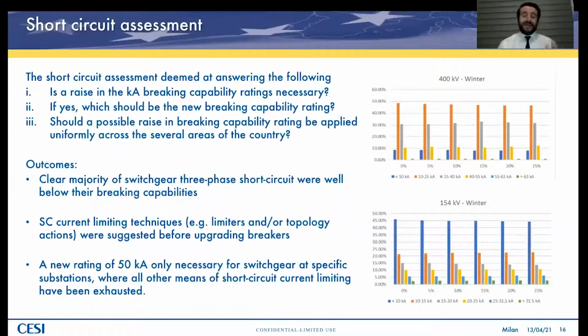Short circuit was at the time one of the major concerns for TEIAS, because the short circuit current, the short circuit power of some substations was moving very fast, closely to the breaker capacity, so to the limit imposed by the equipment, the breakers installed in that substation. So the question that was answered was if an overall upgrade all over the country of the circuit breakers was actually needed, or if only some portion of the grid or some substations could have been upgraded because they needed to, and others could be safely kept on operating with the existing equipment.